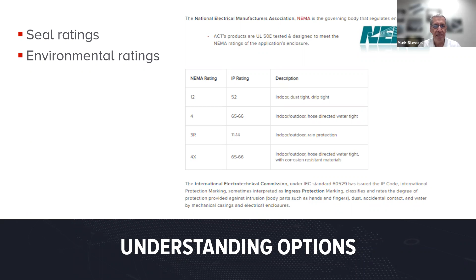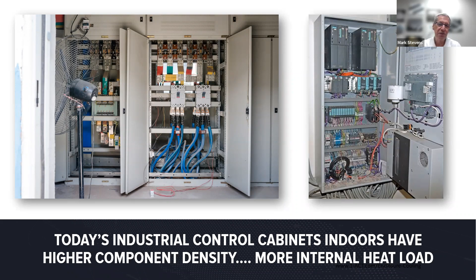A lot of times when you're out and about looking at cabinets in the field, probably one of the biggest mistakes you'll see in an industrial plant is doors left open to try to cool them with a fan. This isn't really good for the equipment, and it's quite dangerous because of arc flash and other risks you could run into. So by keeping the doors open, you're really not serving the electronics or any of the controls well.